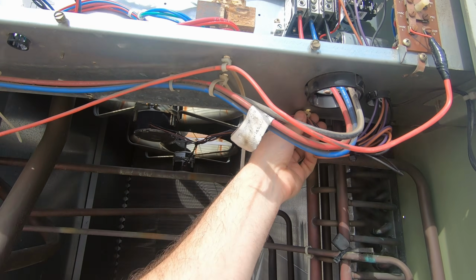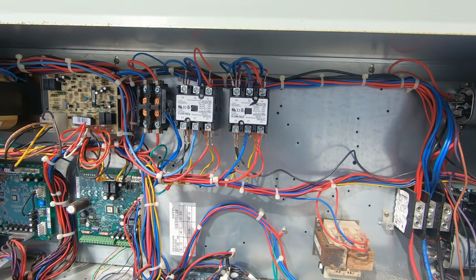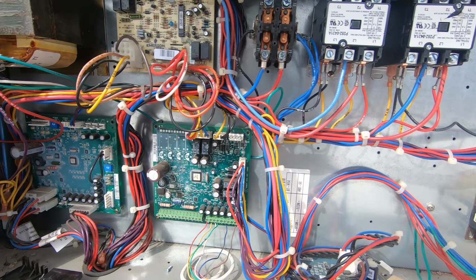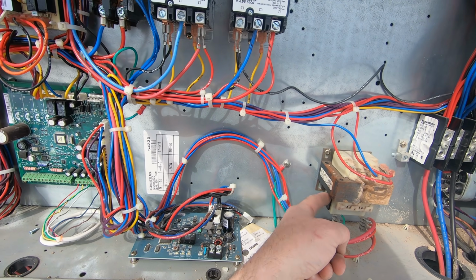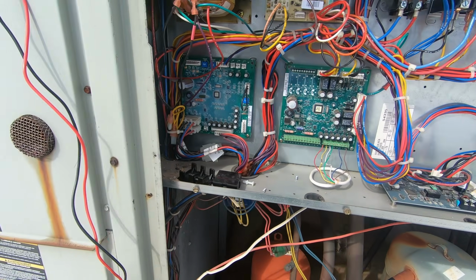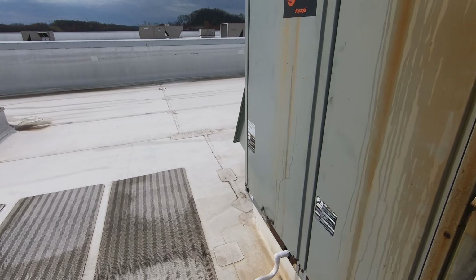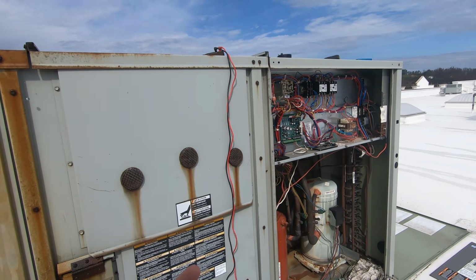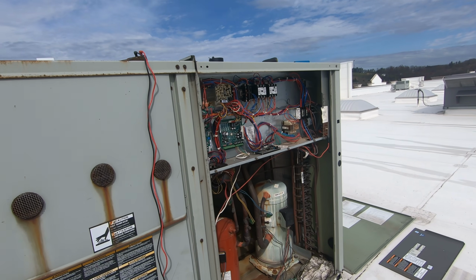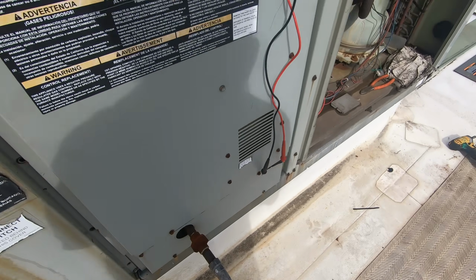I've got everything pinned up and I'm happy with that. Everything looks good. So I'm gonna go ahead and reset my transformer, and we're gonna re-energize the unit and see - is that transformer just gonna pop the 3 amp fuse right off the bat? We'll find out.